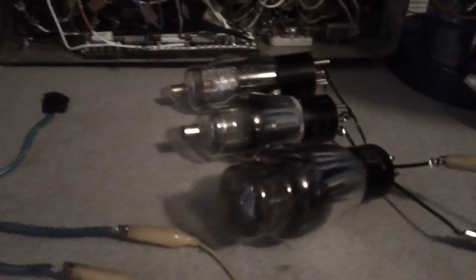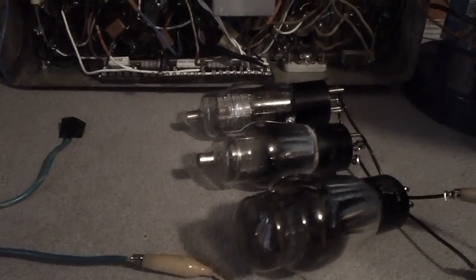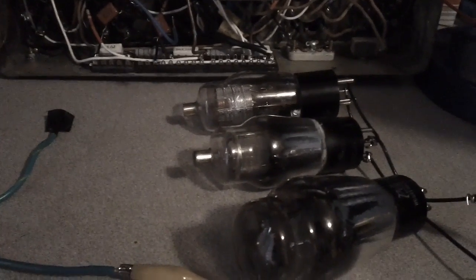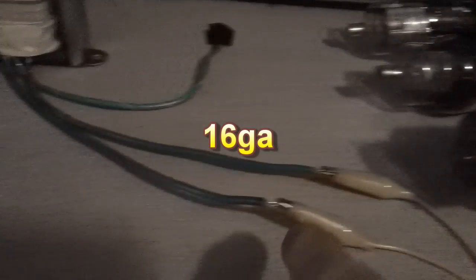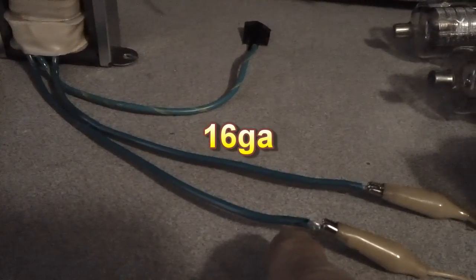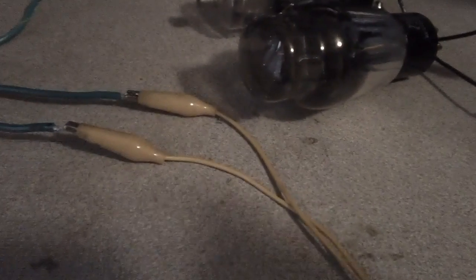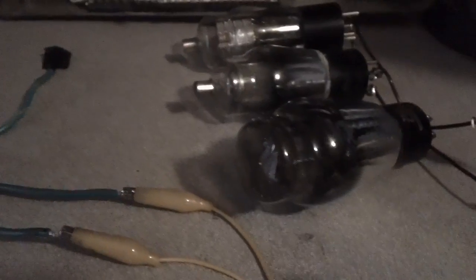It's these jumper wires. They're too thin to handle the current draw of these 3 tubes. These 3 tubes draw 5.25 amps total. The 14 gauge wire can handle it, but this cannot. So if I take and hook the 14 gauge wire back to this very large wire, because this is a 10 amp rated connection, it's got very thick wire. If I connect those two back together and eliminate these thin gator wires, these things should light up again.